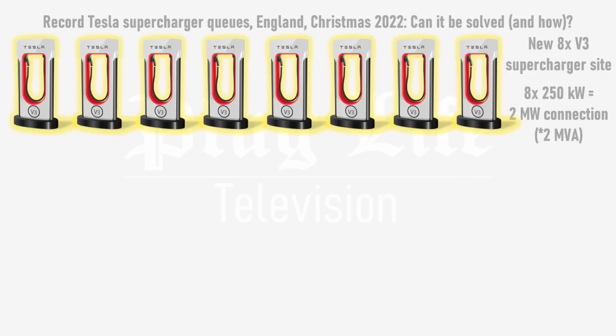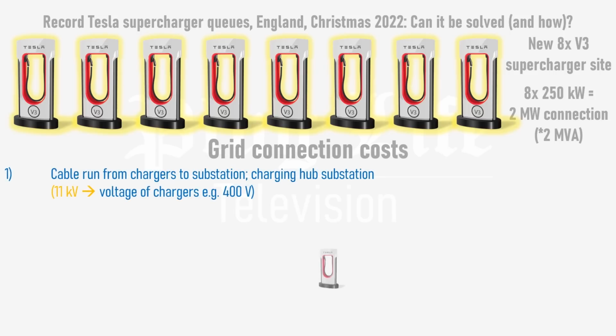This requires a 2 megawatt grid connection. Well, I've approximated it to 2 MVA, but I won't confuse you with power engineering stuff for now, let's assume it means the same thing. To connect the superchargers to the grid, they will require a substation that converts voltage from the distribution grid, which is 11 kilovolts, to the input voltage of the chargers, which is around 400 volts.